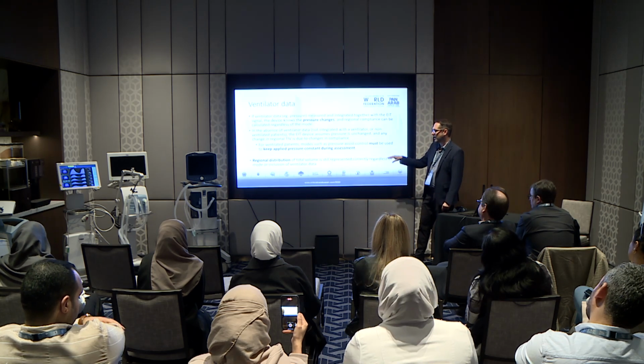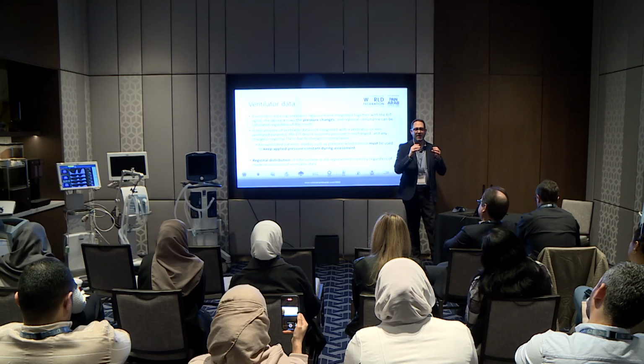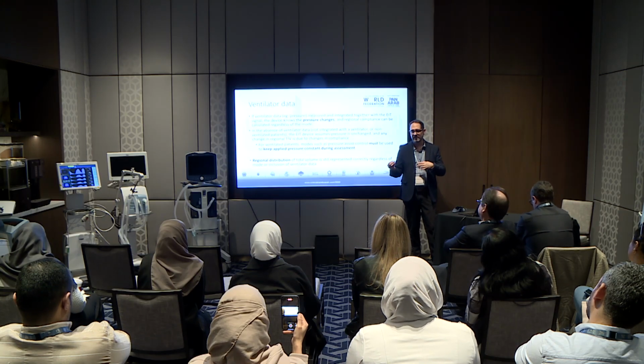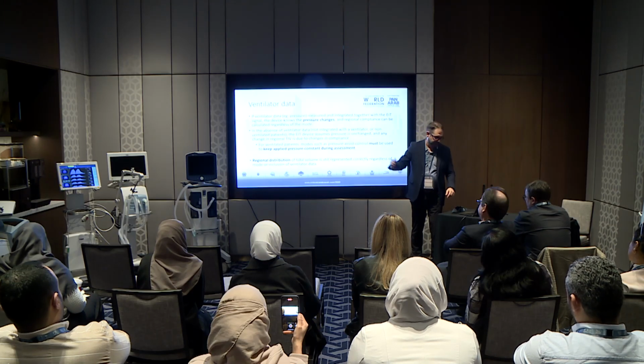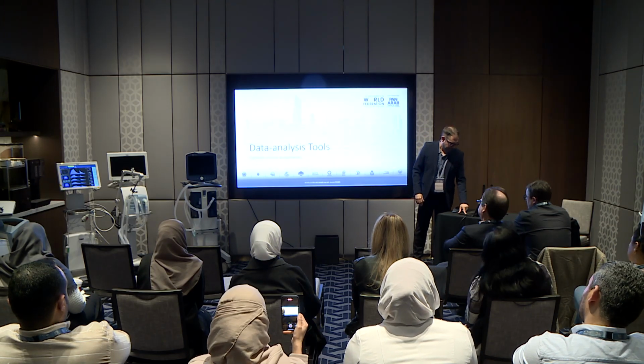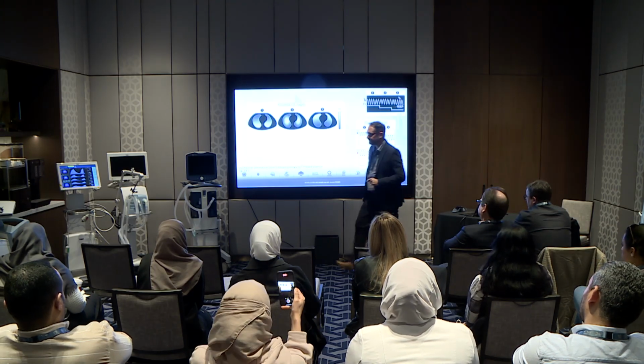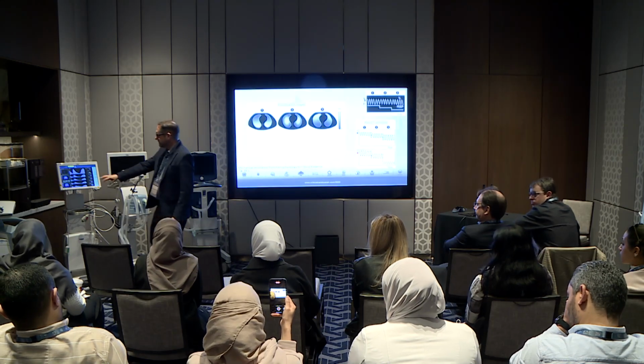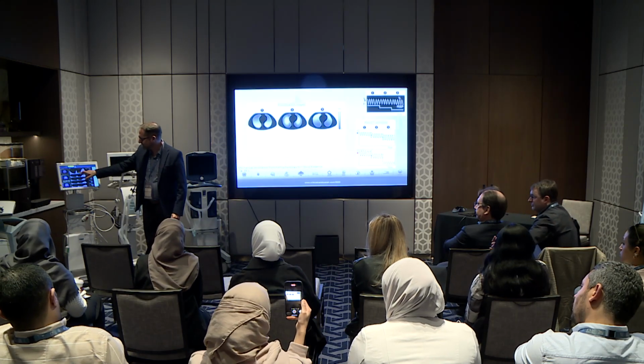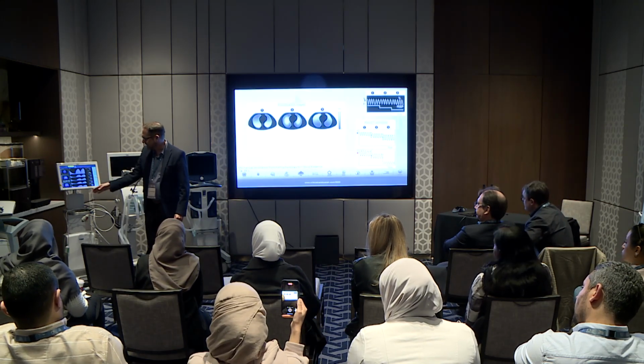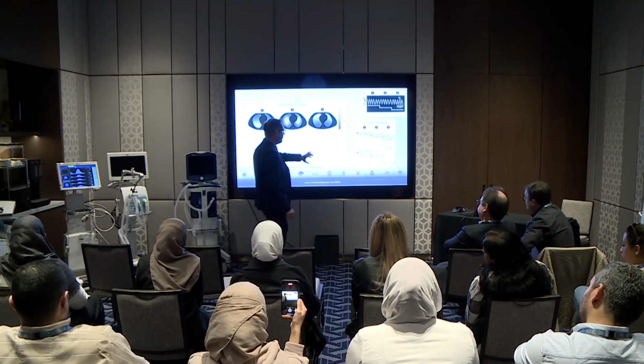Regional distribution of tidal volume is still represented correctly regardless of the mode. So the distribution does make sense. It's just calculating compliance or changes in compliance is not accurate if pressure is changing and the device doesn't know that it's changing. Some of the things that we can utilize. So again, I can see the height that's changing and increasing and going back down again.